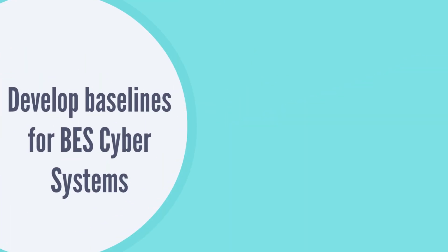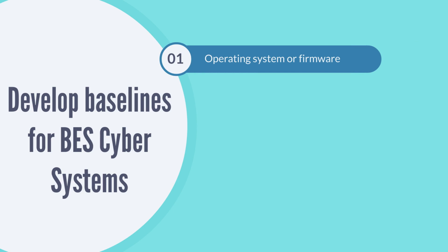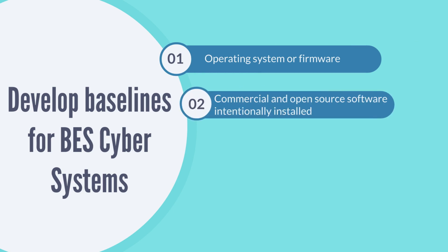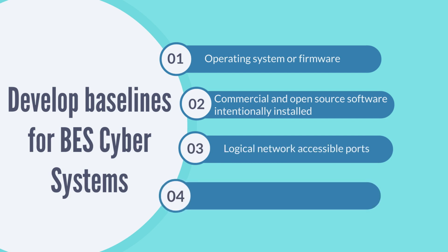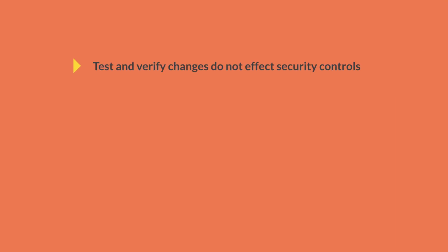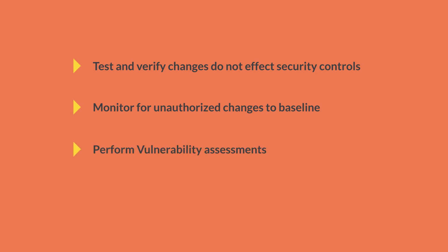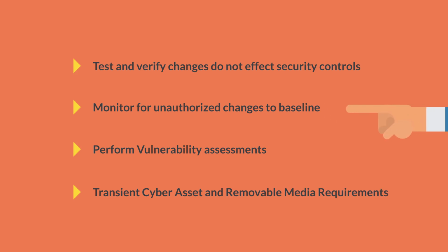Develop baselines for BES cyber systems: operating system or firmware, commercial and open source software intentionally installed, logical network accessible ports, security patch level. Test and verify changes do not affect security controls. Monitor for unauthorized changes to baseline. Perform vulnerability assessments. Transient cyber asset and removable media requirements.